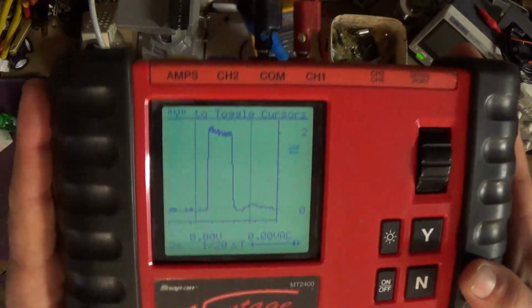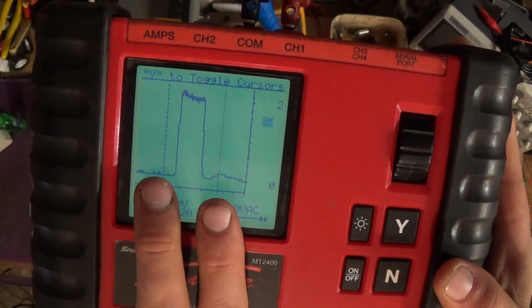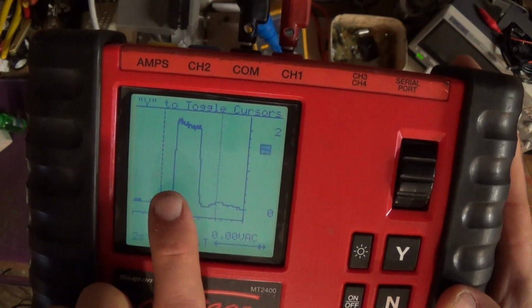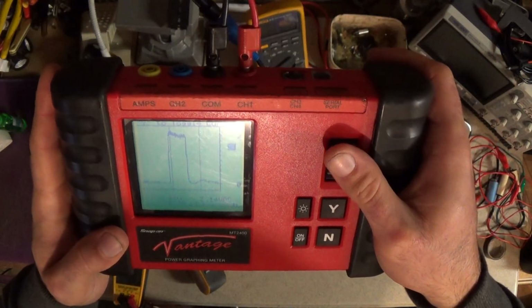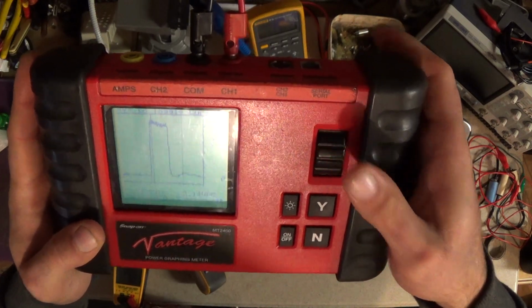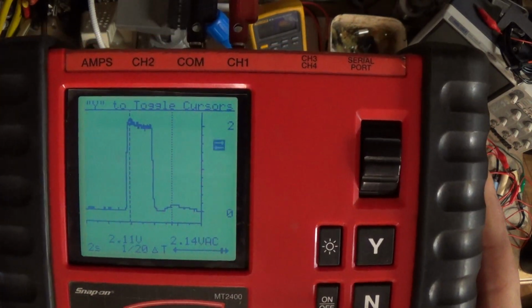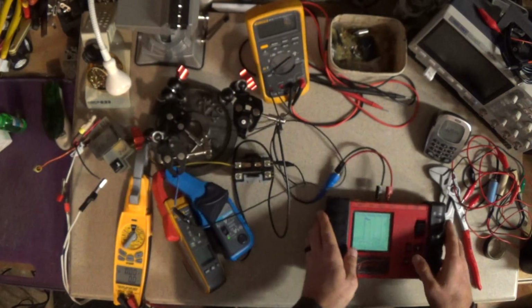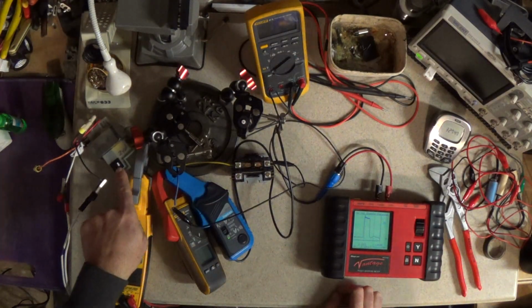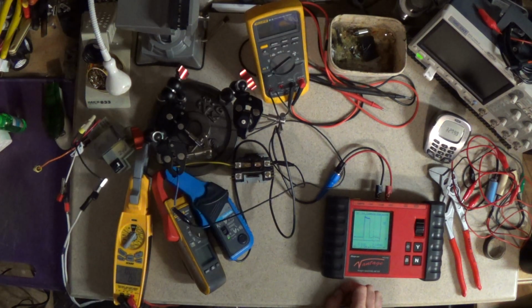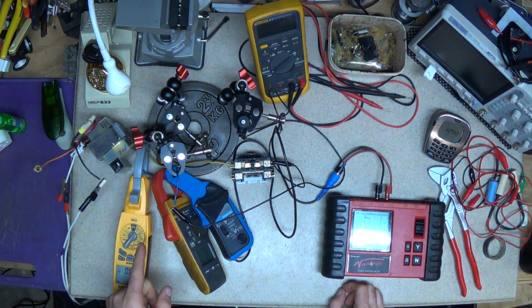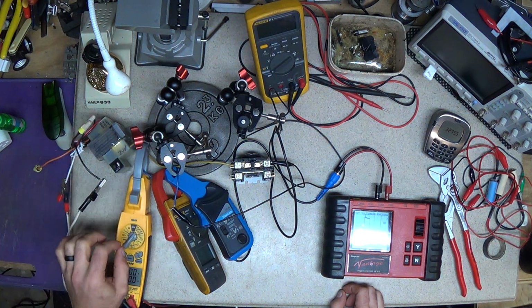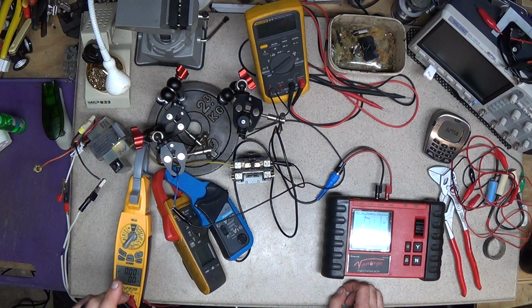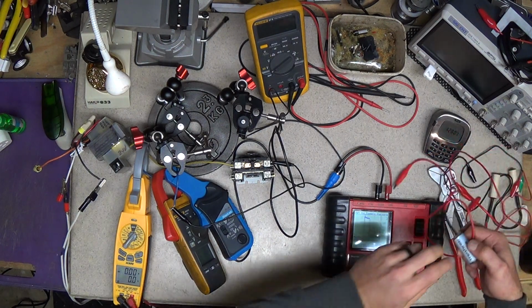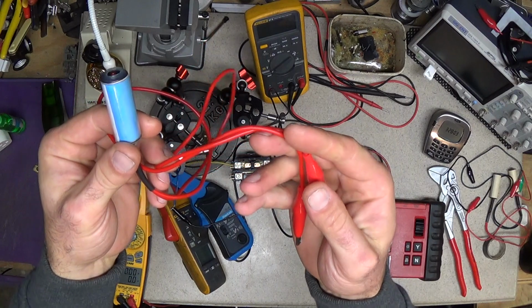Alright, right here - look how much more time a circuit breaker allows a short to exist than the PTC. Also look at the peak - we're at 21.1 amps. So this circuit breaker, and it was this one that tripped, not this one - the circuit breaker the manufacturer put into the transformer is way more abusive than this PTC device.